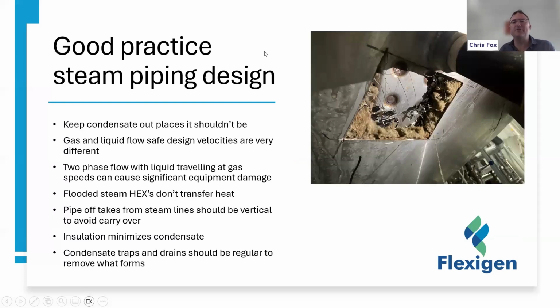And lastly, I'll go through this pretty quickly because I know El Sadiq and Michael will probably talk about it. But the biggest thing in my experience in terms of designing an efficient and reliable steam network is keep condensate, and for that matter, any particulates that shouldn't be there, out of the network. Gas and liquid flow safe velocities are very different. So a safe velocity for gas can be as high as 30 meters per second. Safe flow for liquids like 5 meters per second. So if you have two-phase flow caused by condensate forming in your steam system, you're going to be sending condensate at 30 meters a second, which is a lot denser and heavier than the steam, and it's going to hit stuff hard, and that causes problems over time.